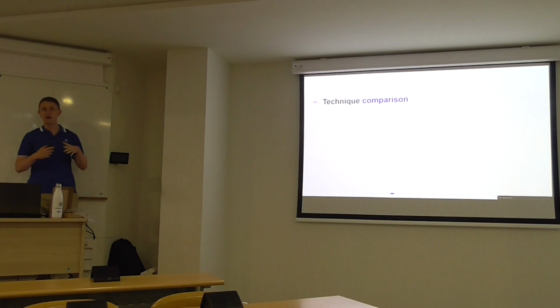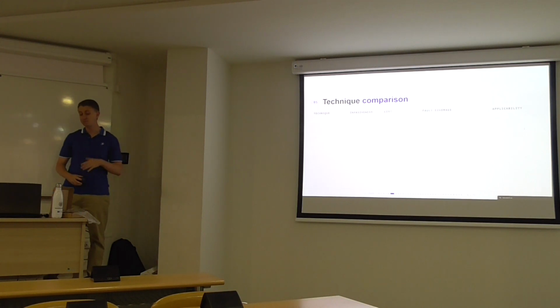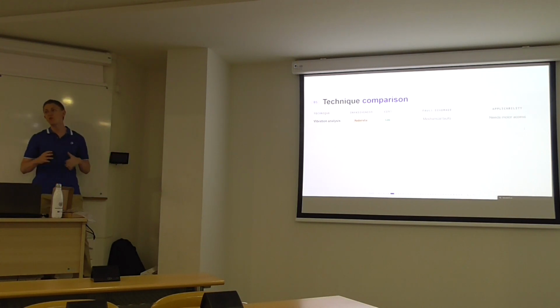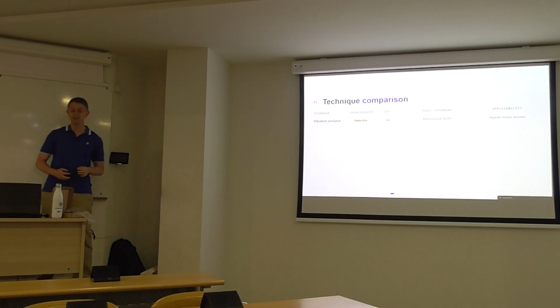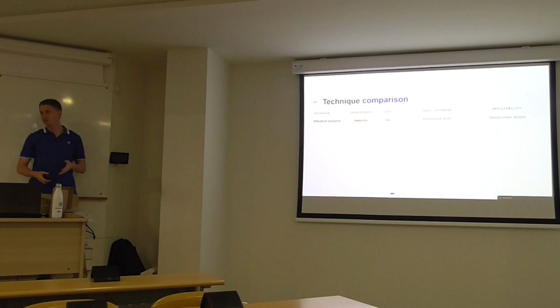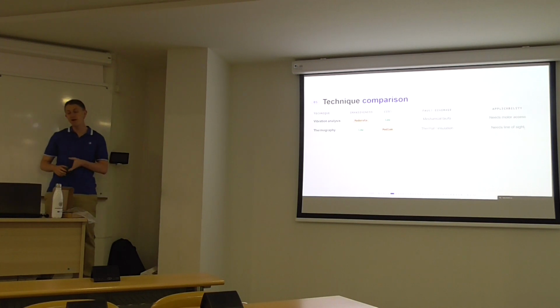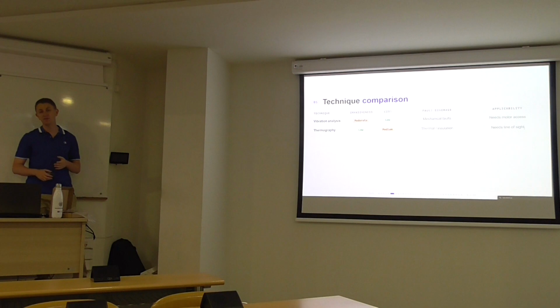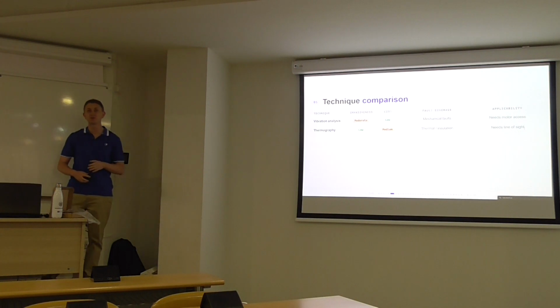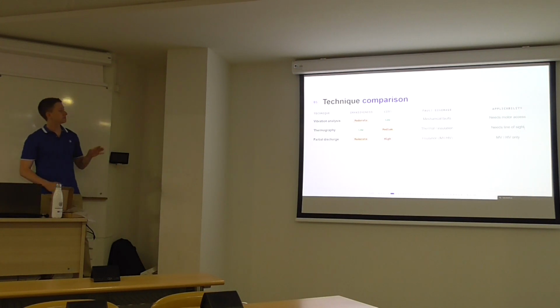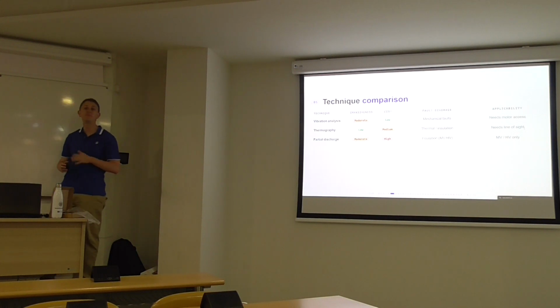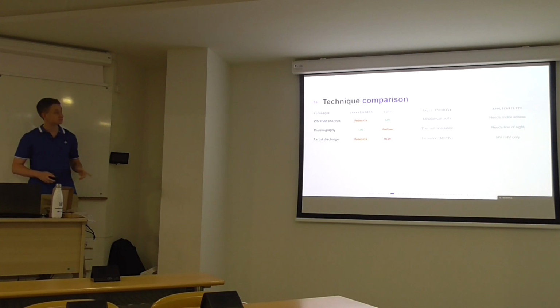Well, now just a quick comparison between the techniques. In vibration, we have a moderate invasiveness because we need to access the motor housing to place the sensor. The cost is very low, sensors are not that expensive, and we cover mechanical faults. With thermography, the invasiveness is maybe lower, but the cost is higher because of the equipment, and we cover thermal and insulation faults. Then with partial discharges, the invasiveness is moderate, the cost is higher, and we are covering insulation faults in medium to high voltage machines.